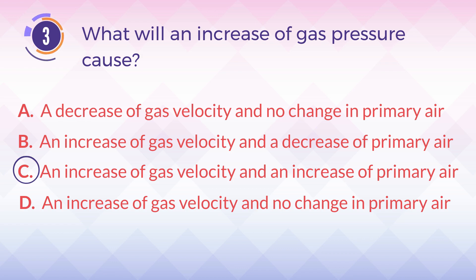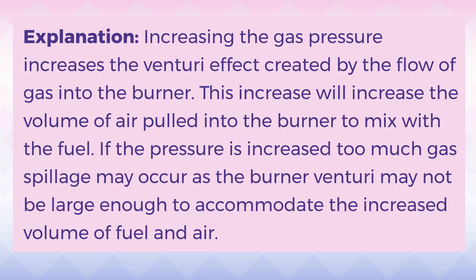The answer is C: an increase of gas velocity and an increase of primary air. Increasing the gas pressure increases the venturi effect created by the flow of gas into the burner. This increase will increase the volume of air pulled into the burner to mix with the fuel. If the pressure is increased too much, gas spillage may occur as the burner venturi may not be large enough to accommodate the increased volume of fuel and air.